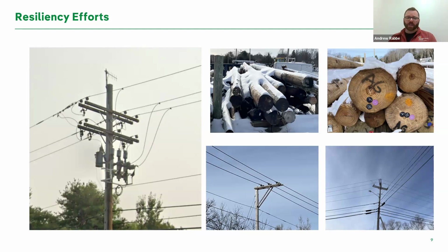This device on the left here is the same thing down the line. The goal, I think, is eventually to have a device like this on the 3-phase backbone every 500 customers. So instead of the station breaker opening and going to lockout for something all the way at the end of the line, you're going to have one of these devices in there every 500 customers. You'll be able to sectionalize just a block of 500. Instead of losing 1,500 customers, you're only going to lose 500, close in from one side, and hopefully you have a tie you can close in from the other side and just isolate the outage.